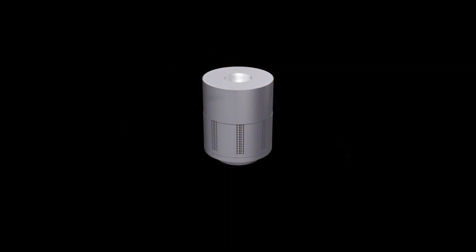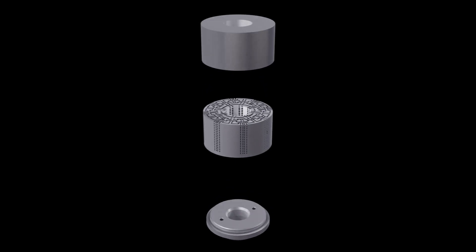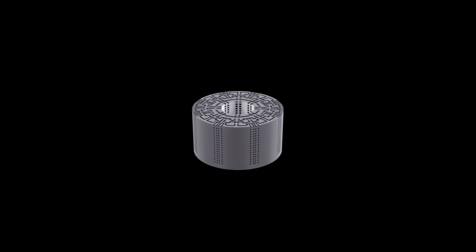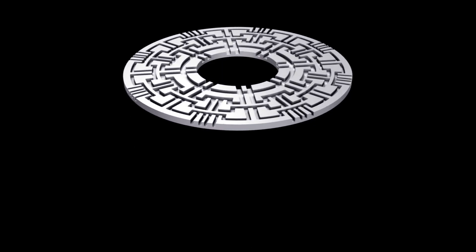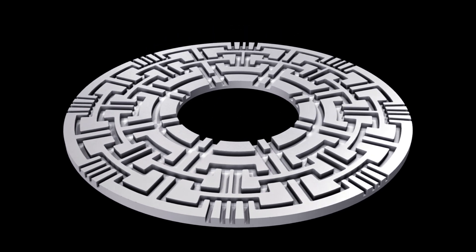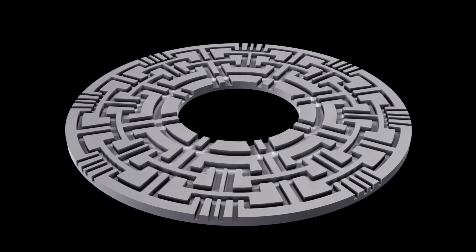Raven Trim is formed by bonding individual discs together in a single-disc stack assembly. Each disc has a pattern of flow orifices and a multitude of channels etched onto the surface, which provides a torturous flow path for the fluid.